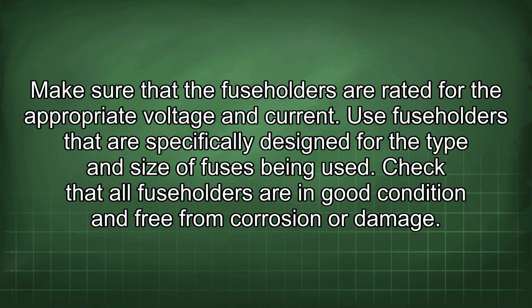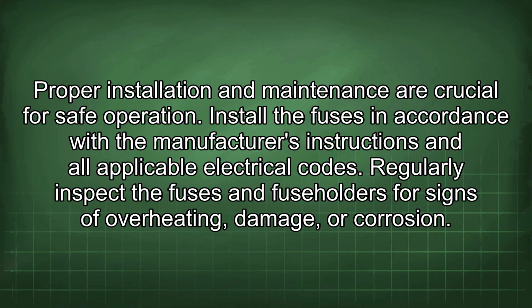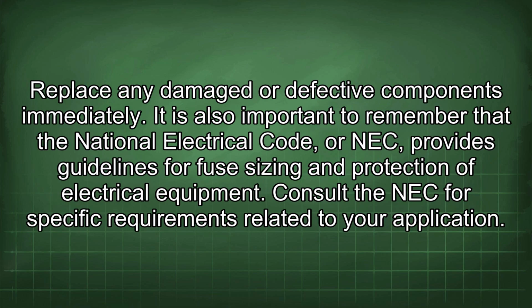Make sure that the fuse holders are rated for the appropriate voltage and current. Use fuse holders that are specifically designed for the type and size of fuses being used. Check that all fuse holders are in good condition and free from corrosion or damage. Proper installation and maintenance are crucial for safe operation. Install the fuses in accordance with the manufacturer's instructions and all applicable electrical codes. Regularly inspect the fuses and fuse holders for signs of overheating, damage, or corrosion. Replace any damaged or defective components immediately.